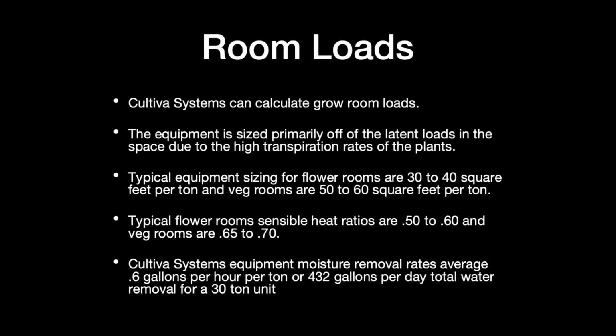The equipment sizing for flower rooms, and this will give you an idea, is you're generally looking at 30 to 40 square feet per ton. So it is a very, very heavy load. The veg rooms, as we said, they're a little less, the load is a little lower. You're looking at 50 to 60 square feet per ton.